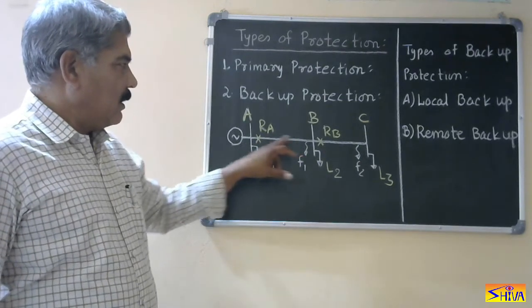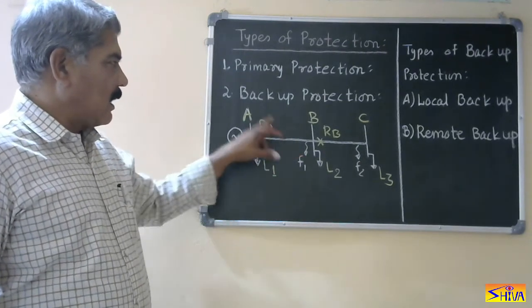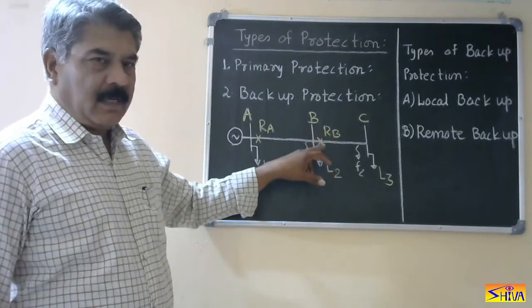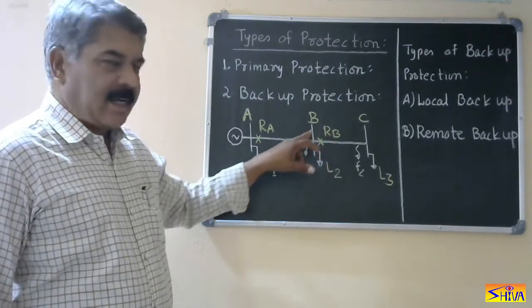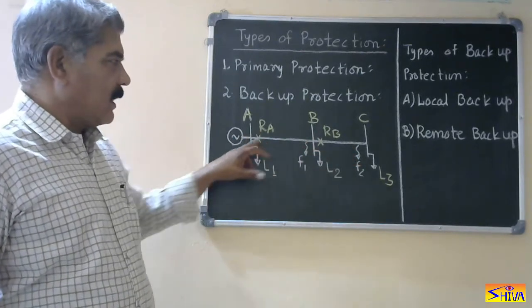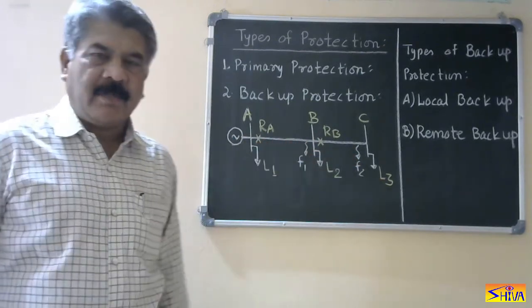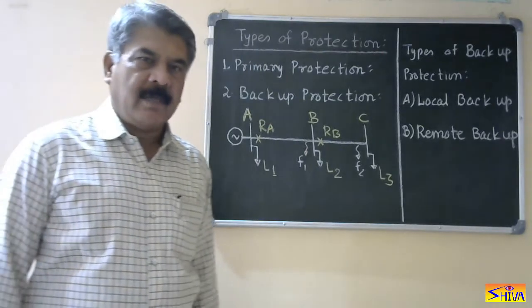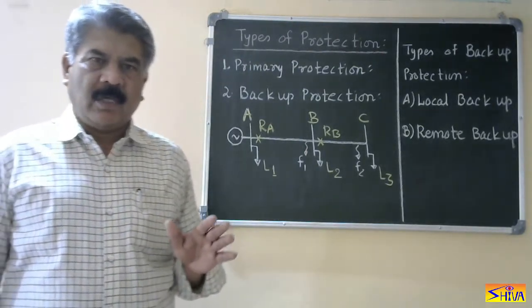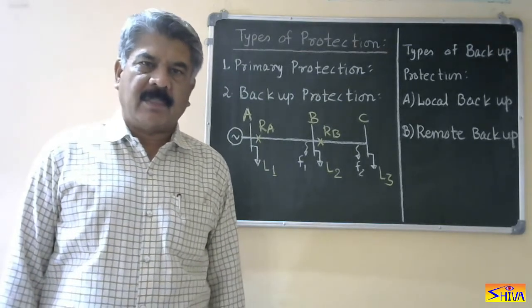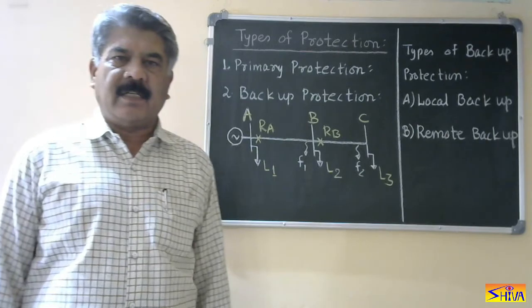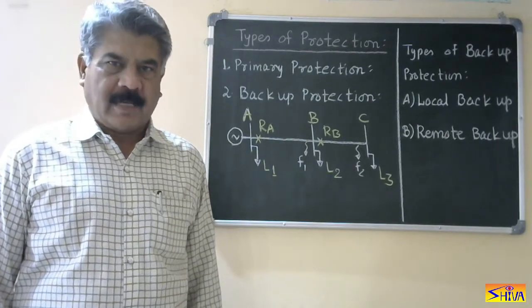For section A-B, relay R-A is used. For section B-C, relay R-B is used. So R-B is acting as primary protection to section B-C, and R-A is acting as primary protection to section A-B. Primary protection is provided to every equipment of the power system — it is the main, essential protection and it operates in the least possible time.